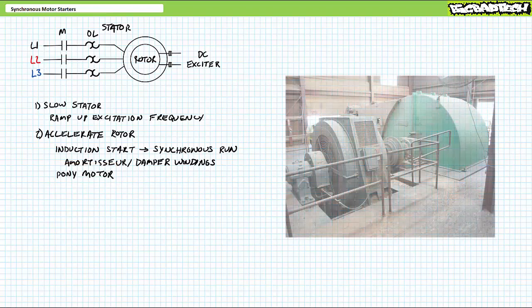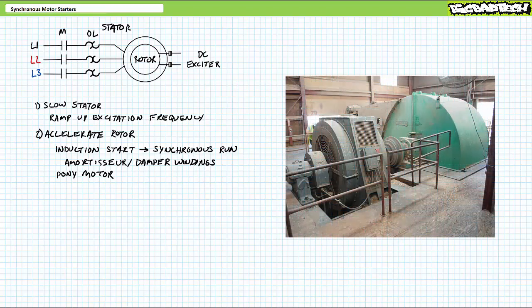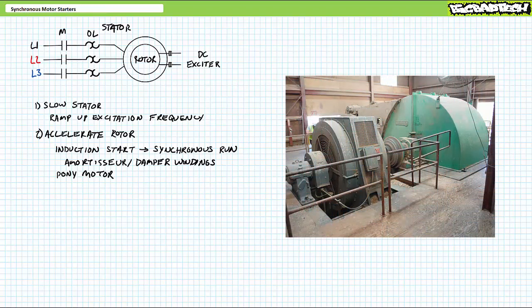Consider some giant 1,000 horsepower synchronous motor with a large number of pole pairs suitable for exerting high torque at low speeds. Such a massive rotor would have obvious difficulties accelerating to synchronous speed. For this reason, a smaller induction style or DC motor mounted on the same shaft is energized and used to get just the rotor turning. Once it accelerates to near-synchronous speed, the rotor field is energized, which locks into the stator's rotating magnetic field.